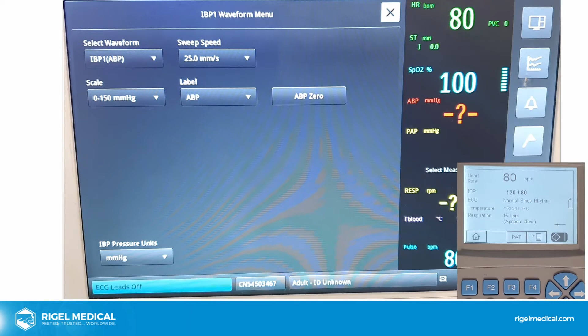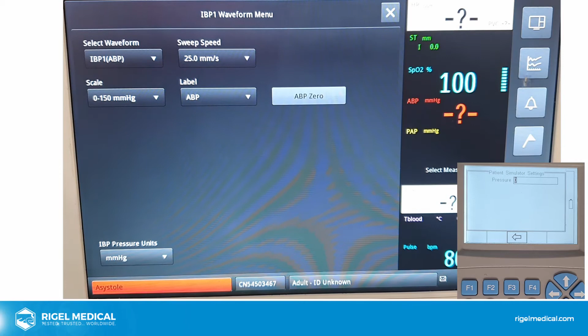For IBP though, we need to do a 0 for this, and to do that we go into the menu on this particular monitor, and on the patient simulator, so if we need to go back to that, we go to the PAT settings, static IBP test, automatically set up for 0, select ABP Zero, it's going to give us a few alarms while we're disconnected.